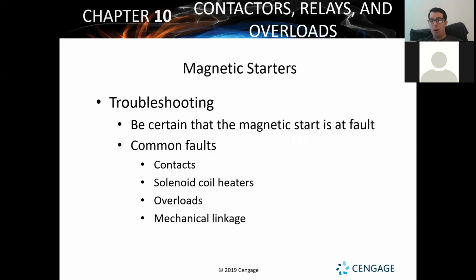Is it opening on high temperature when it needs to? If it opens up on high temperature and the system's not running at really high amperage and it's wintertime, definitely an issue, but if it's a really hard-running system on a hot day, then yes, I would not be surprised if we have an overload activating as it normally would.